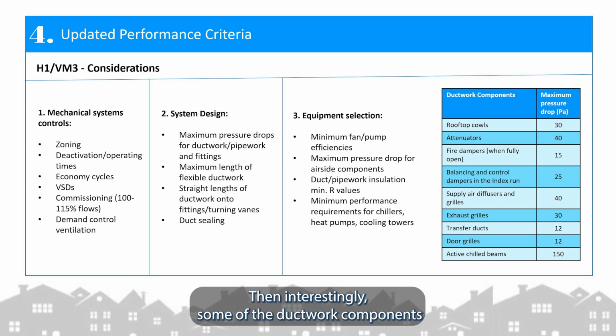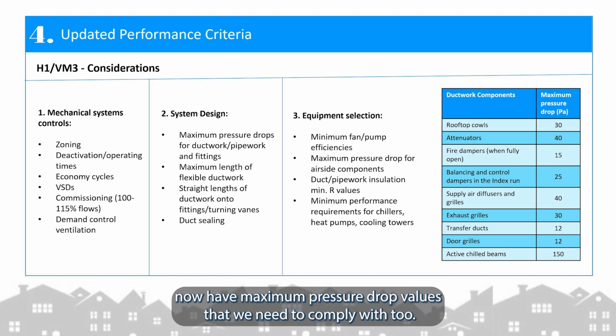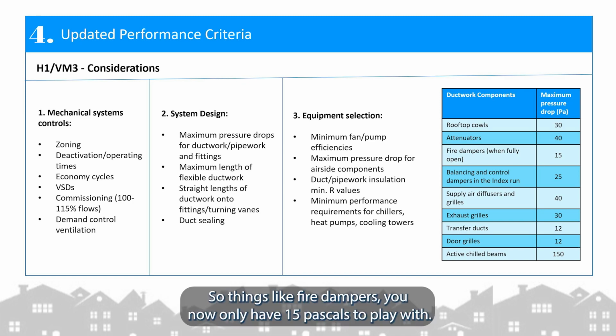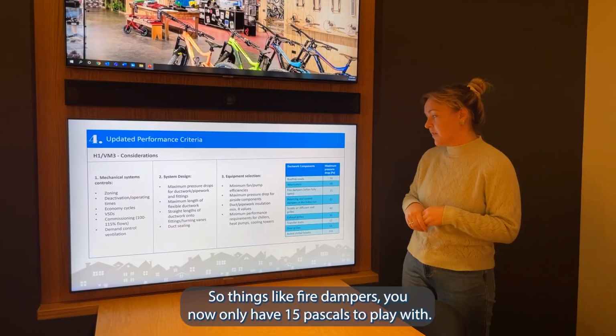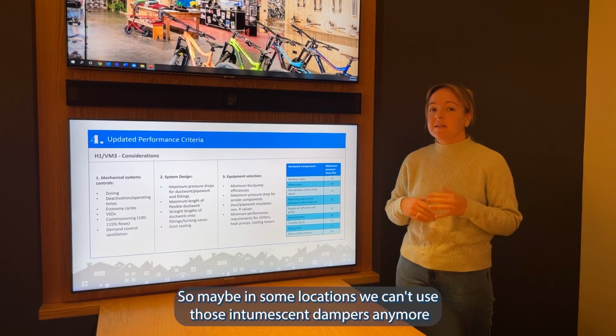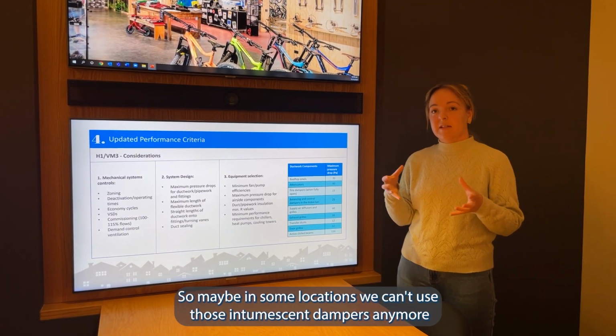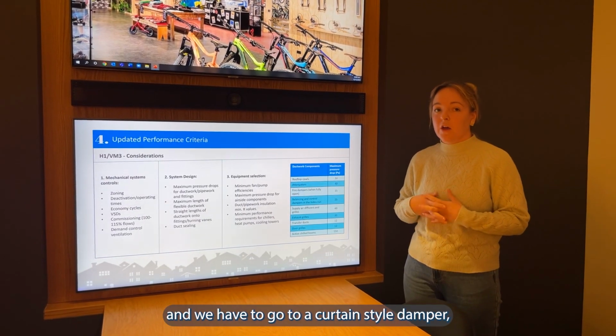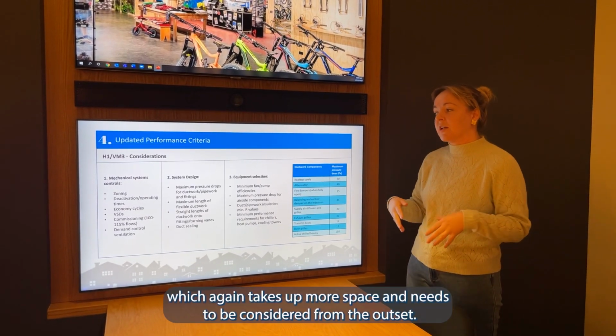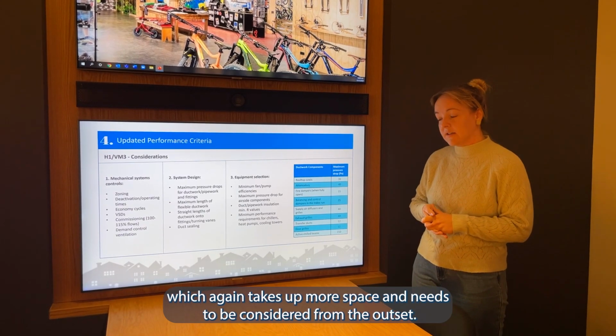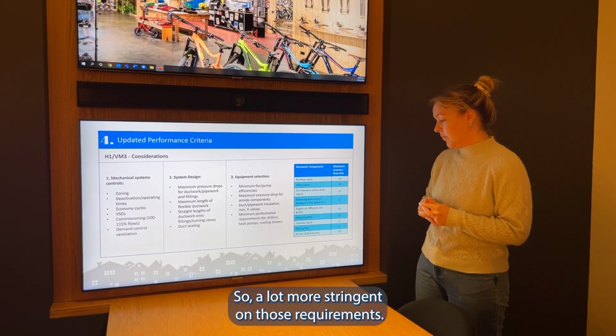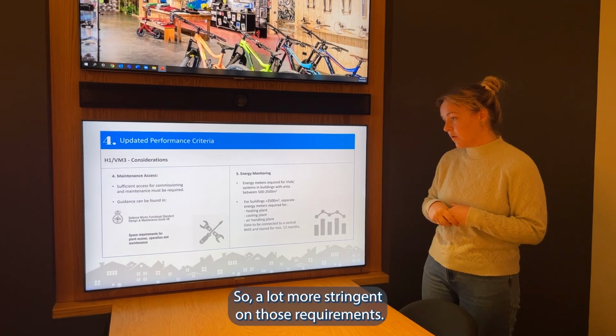And then interestingly, some of the ductwork components now have maximum pressure drop values that we need to comply with too. So things like fire dampers, you now only have 15 pascals to play with. So maybe in some locations we can't use those intumescent dampers anymore, and we have to go to a curtain style damper, which again takes up more space and needs to be considered from the outset. So yeah, a lot more stringent on those requirements.